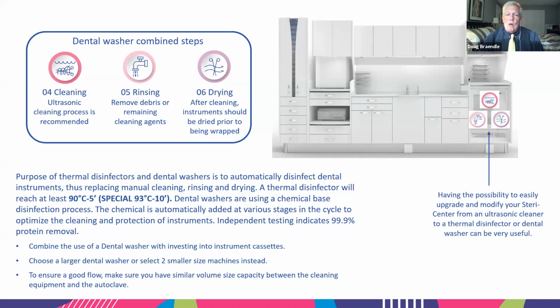And all of us in the sterilizer business, we have an approximate idea as to how long it takes our own machines to complete adequate drying. That can be off as much as 10 or more minutes just if you introduce wet pouches going into the sterilization cycle. So she's 100% on the ball, dry going in, and you'll be dry coming out of a sterilizer.